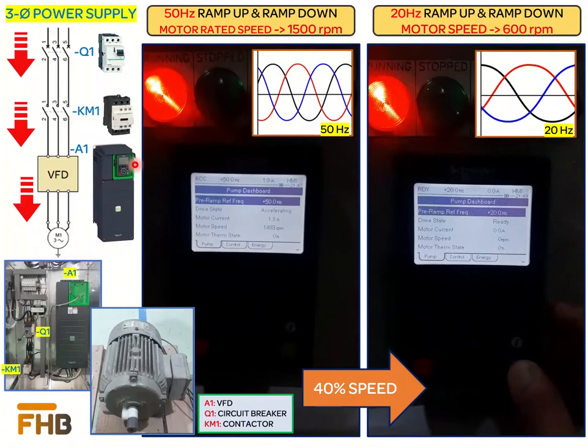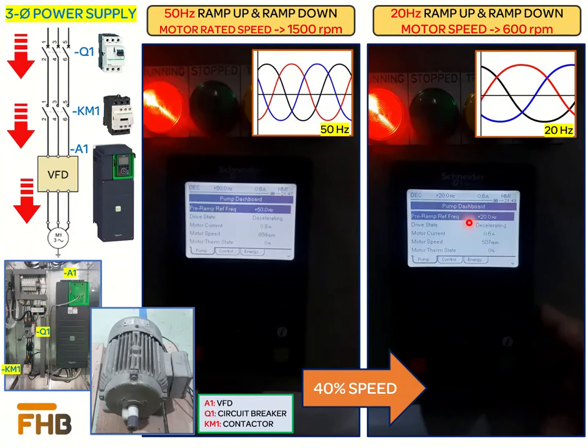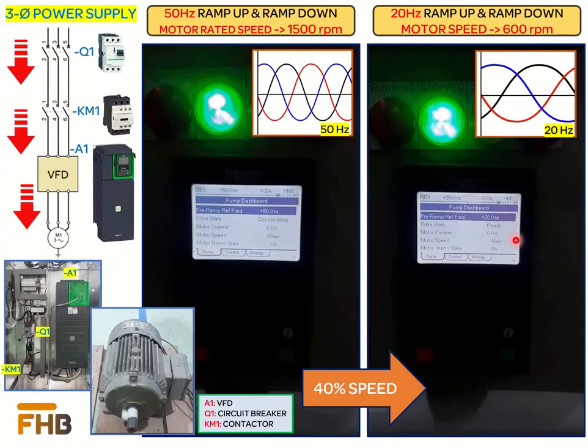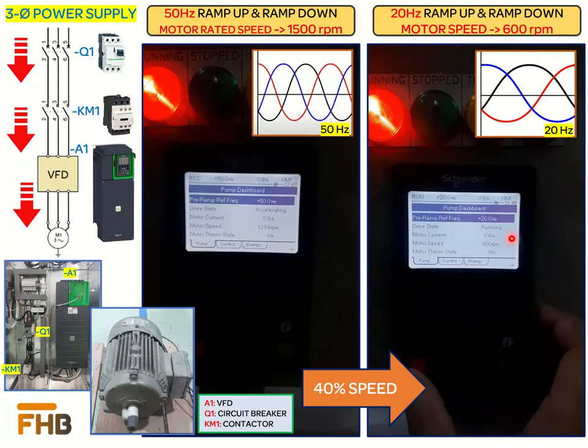In the demonstration, when the reference frequency is set at 50 Hz, the motor ramps up to the rated speed of 1500 rpm. However, when the reference frequency is set at 20 Hz — which is 40% of the rated frequency — the motor ramps up to 600 rpm, which is also 40% of the 1500 rpm rated speed.